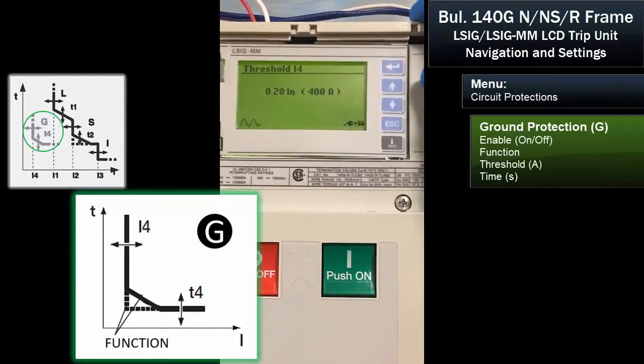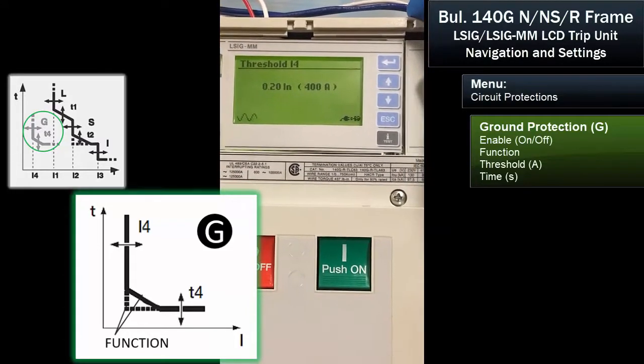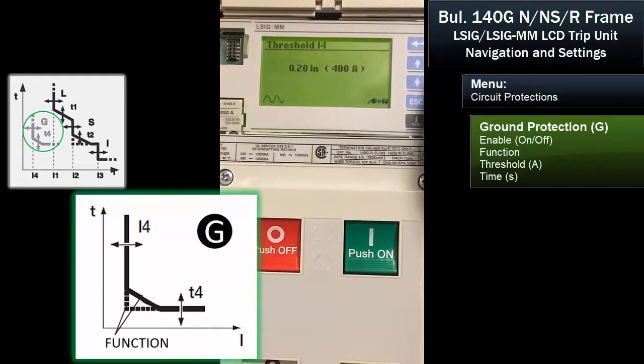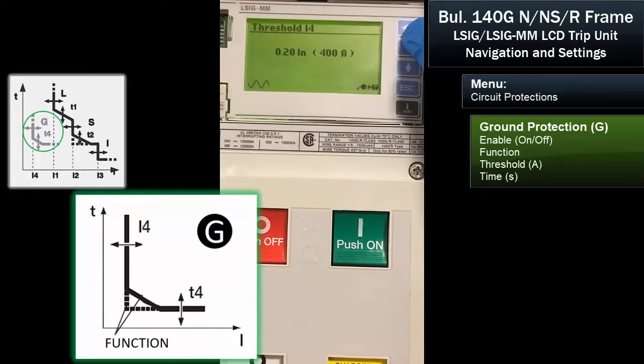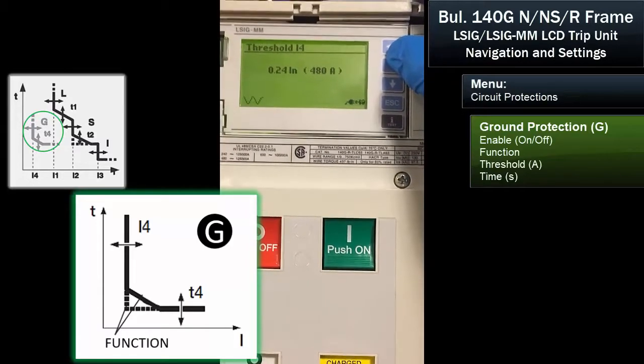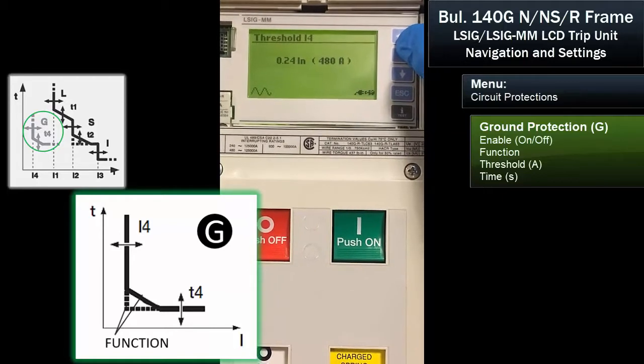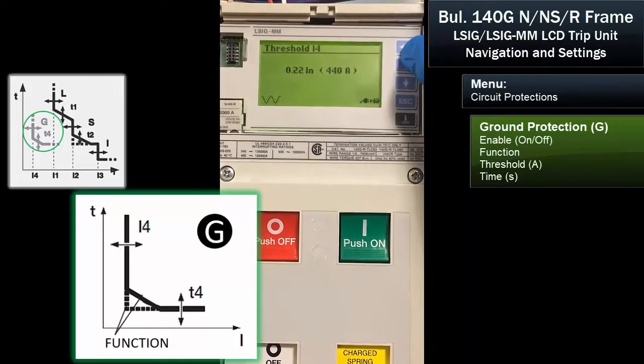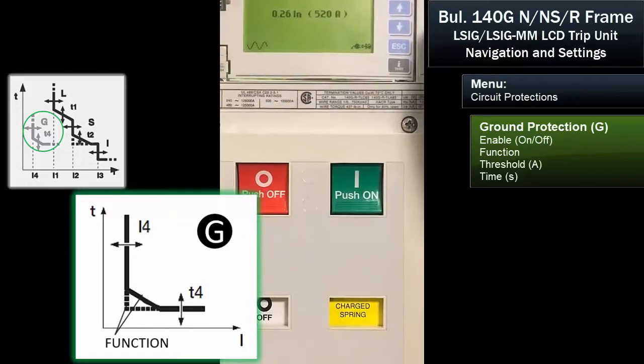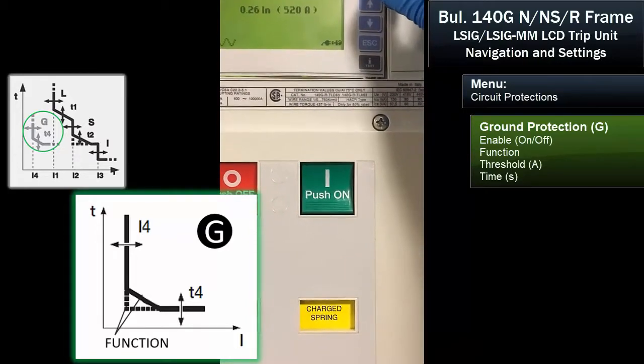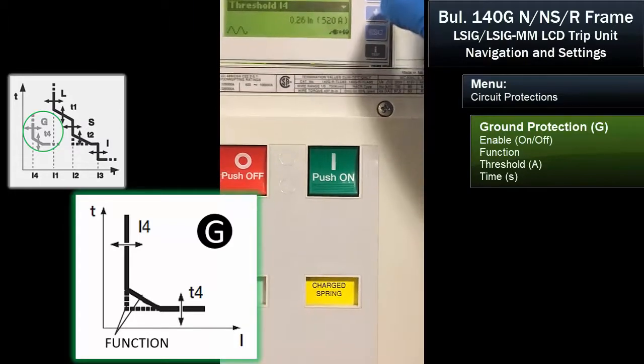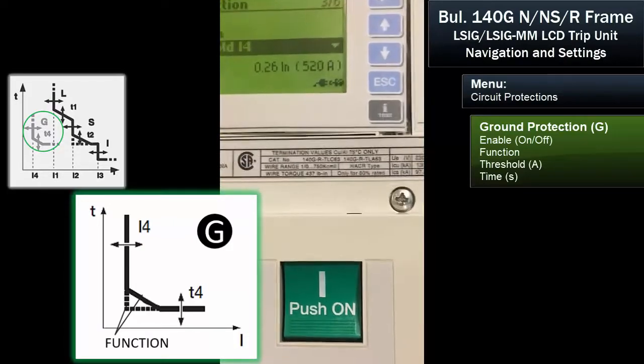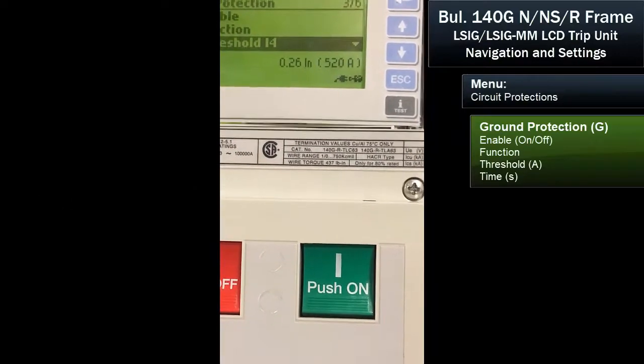Here's the ground fault, or I4, value. This is a 2000-amp breaker, and it's set at 20% of the rating, or 400 amps. Depending on where this is installed, this setting can vary — it can go all the way down to 20% and up to 100% of the rating. Let's leave it at 26%. So it's set for an instantaneous trip on ground fault of 520 amps.